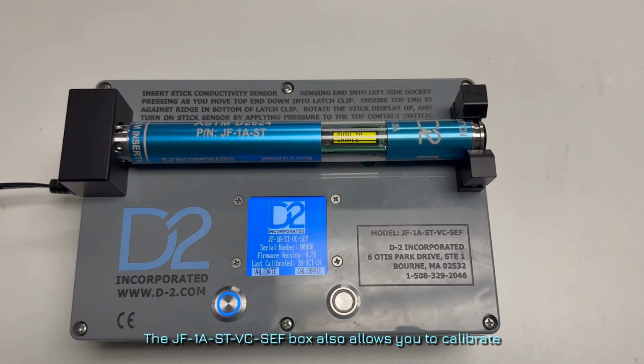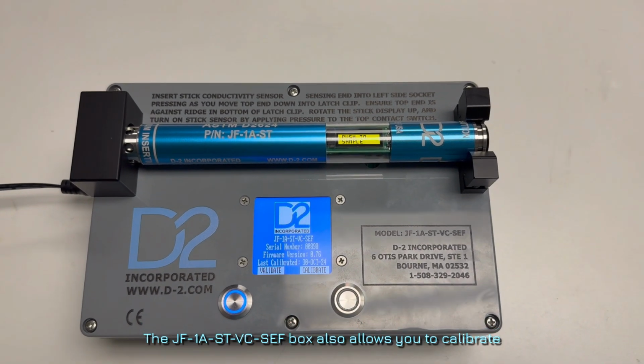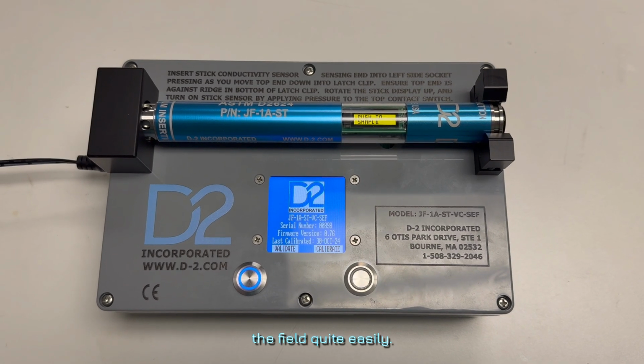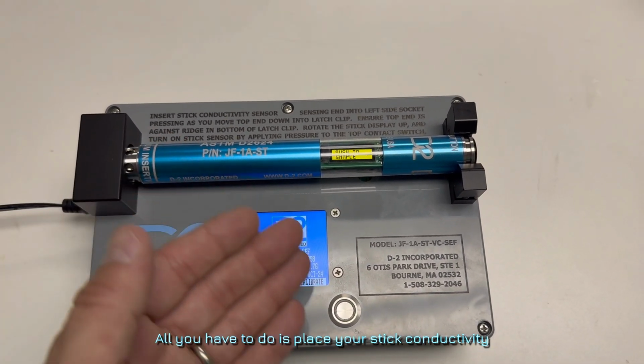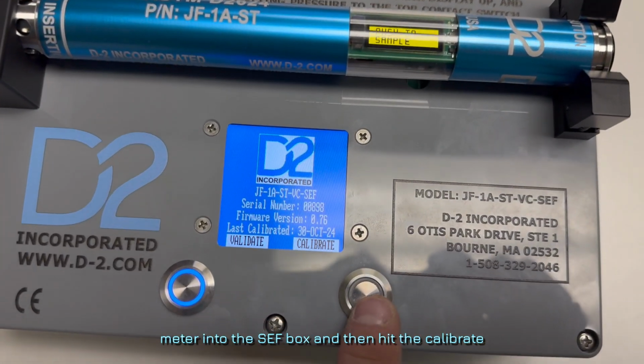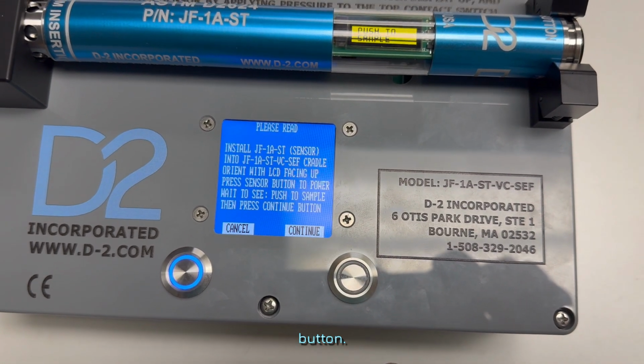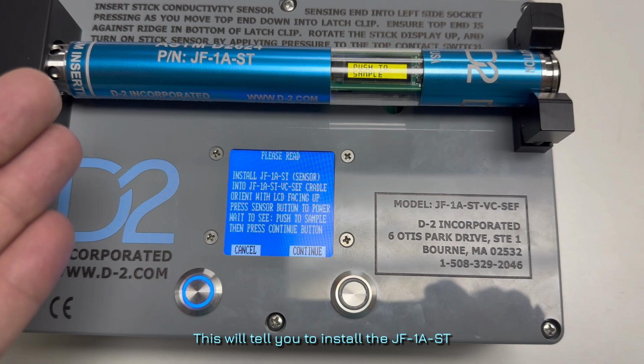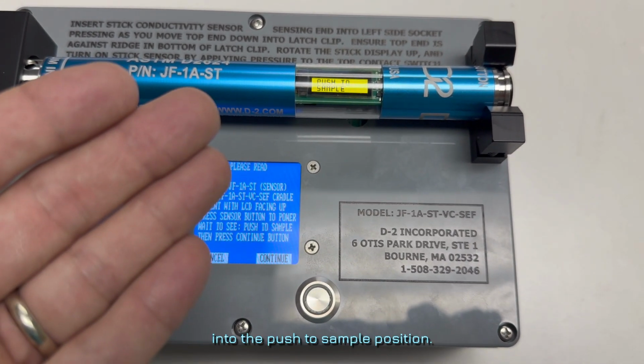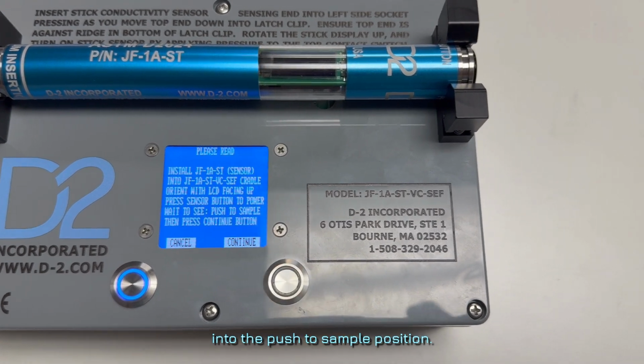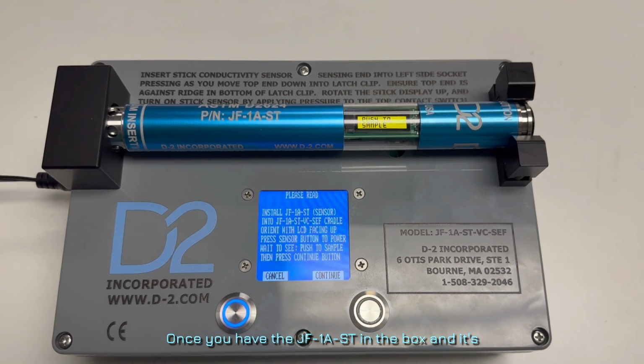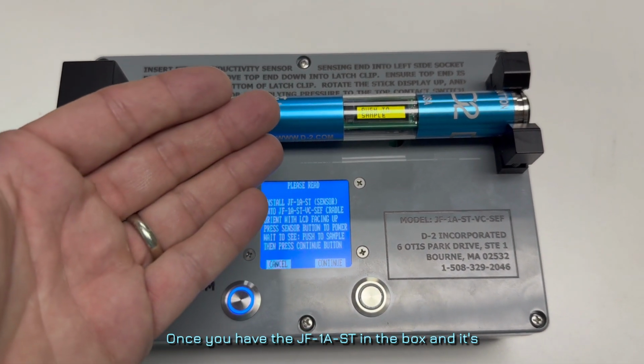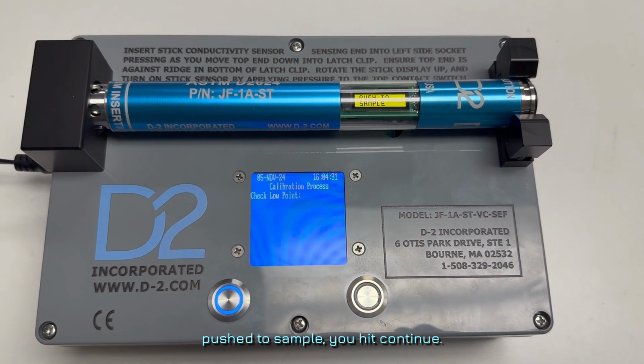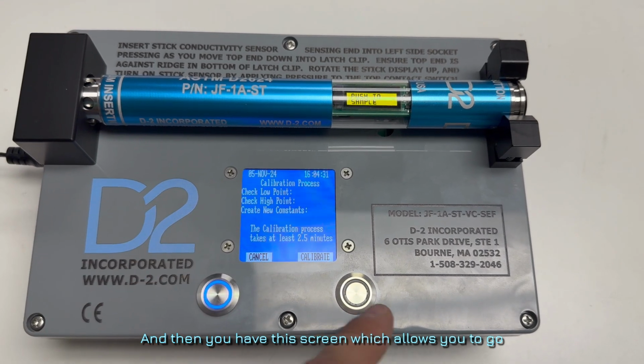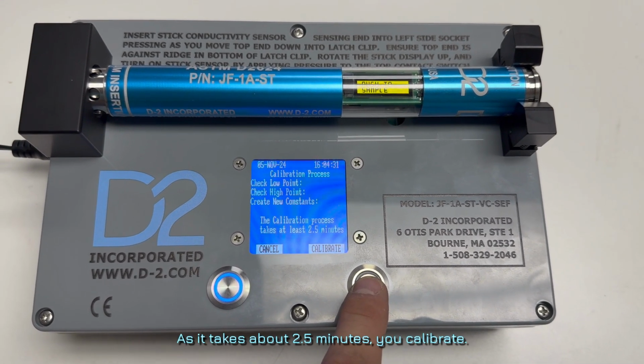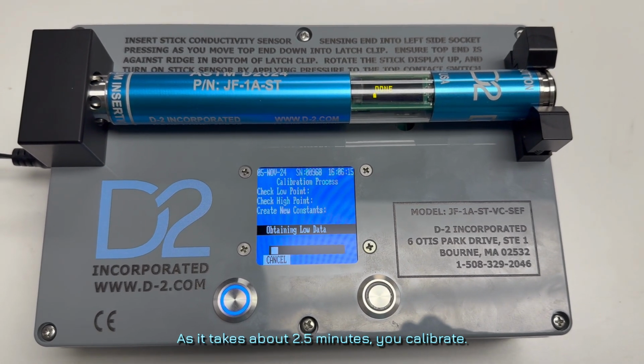The JF1A ST VC SEF box also allows you to calibrate your stick conductivity meter in the field quite easily. All you have to do is place your stick conductivity meter into the SEF box and then hit the Calibrate button. And this will tell you to install the JF1A ST conductivity meter as it is and to have it in the push to sample position. Once you have the JF1A ST in the box and it's at push to sample, you hit continue. And then you have this screen, which allows you to go ahead and calibrate. It says it takes about 2.5 minutes. Hit calibrate.